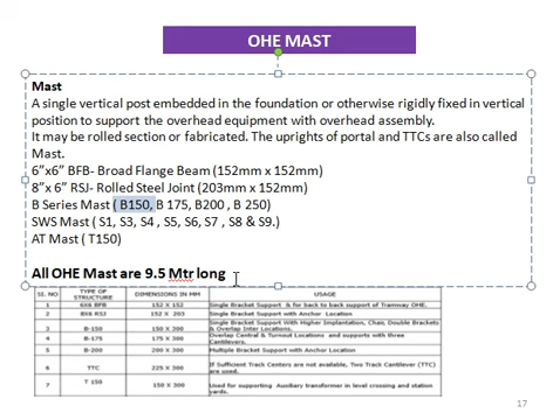Mast is the main vertical post which supports all the overhead equipment. It can be rolled section or fabricated. There are so many types of mast, and it's shown here. This B series mast is normally used in railway: B150, B175, B200, depending upon the width of the mast. And there are fabricated steel masts also, RSJ type, rolled steel joists, BFB type, broad flange beams. These all are used in railway. And one main thing which is common for all the masts: all the OHE masts are of 9.5 meter length. All masts carrying cantilever assembly are of this length, which are buried in the foundation.